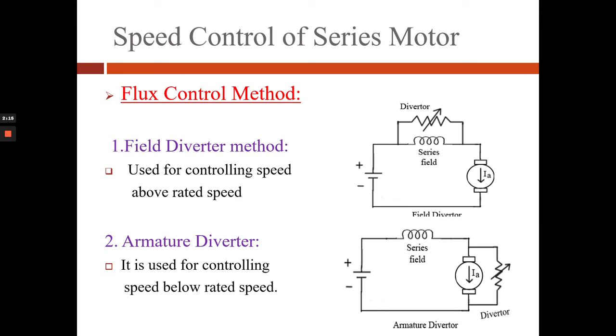Now we will see the flux control method for speed control of DC series motors. The first type is the field diverter method. In this method, a variable resistance is connected across the field winding. This field diverter resistance, being in parallel with the field winding, provides a parallel path for the field current. By adjusting the value of R we can adjust the current flowing through the field winding, and thus the speed can be controlled.